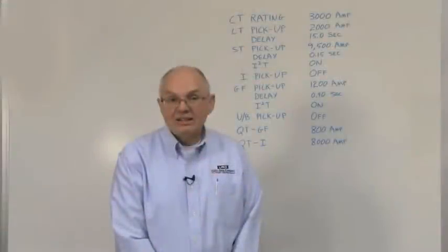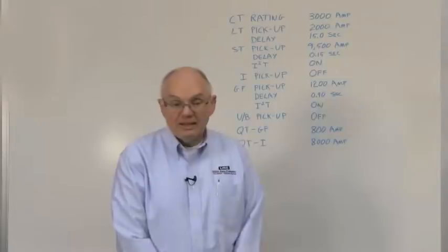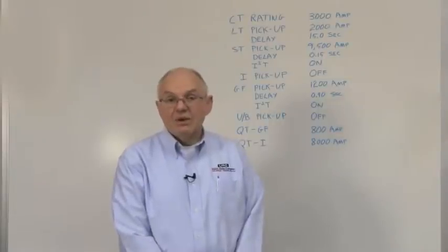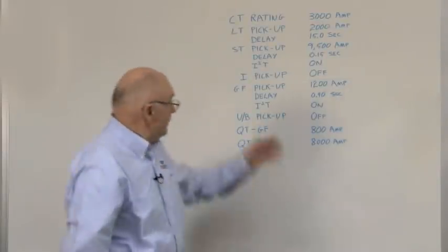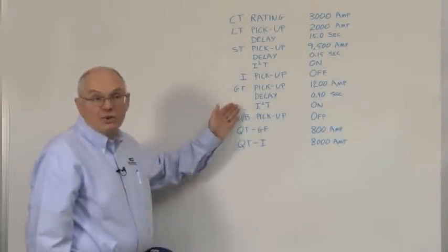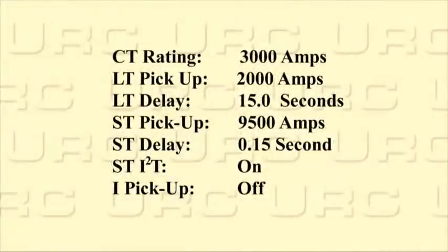If you must change the settings while the breaker is in service, please wear all the appropriate personal protective equipment. Before starting to program the ACPro trip unit, it's best to have all the settings available. These are the settings we're going to program into the trip unit: CT rating 3000 amp, long time pickup 2000 amp, long time delay 15.0 seconds.